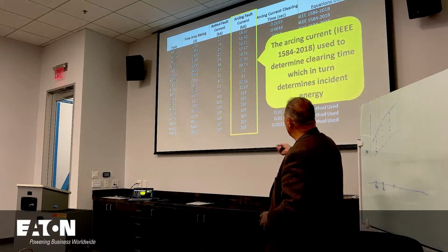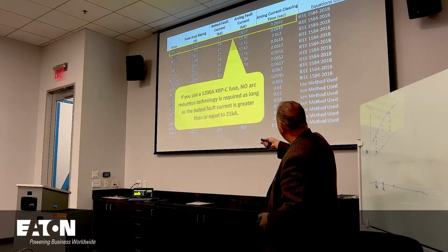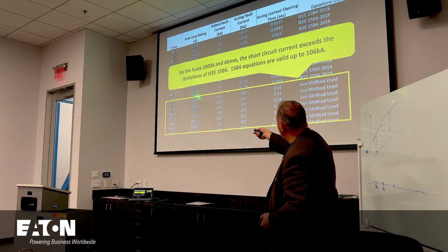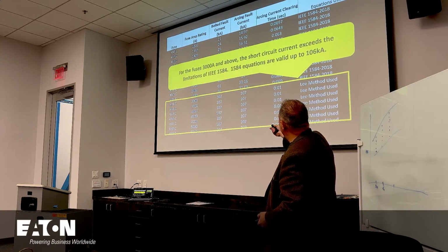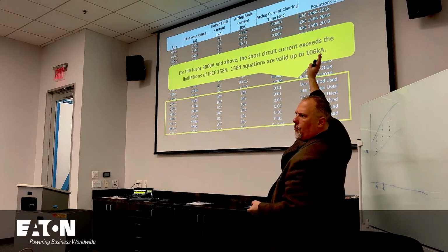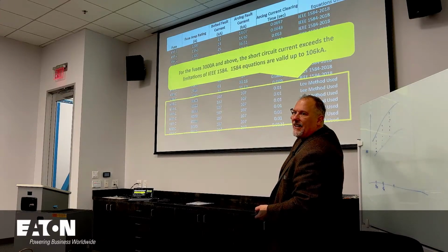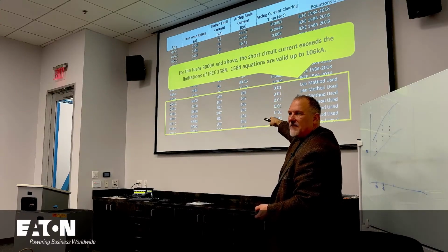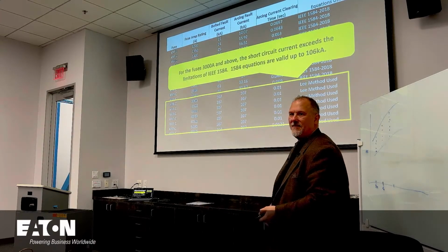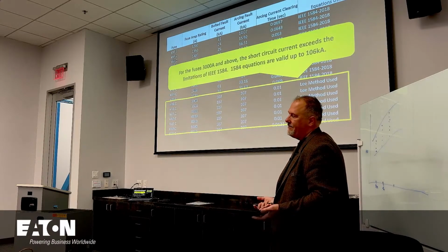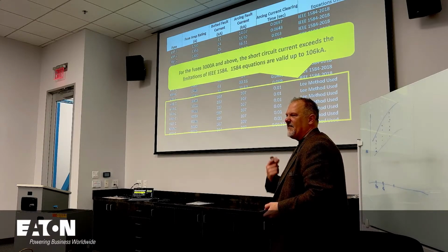So you may be tempted to say, oh, I just did the Lee method. I took an analysis with a 3,500 or 3,000 amp fuse at 106,000 amps, and it said it was way up there, 40 some calories. Then I increased it 1,000 amps to 107,000 amps, and my SKM software said you're down around point some calories. Not right. It left a bad taste in my mouth.